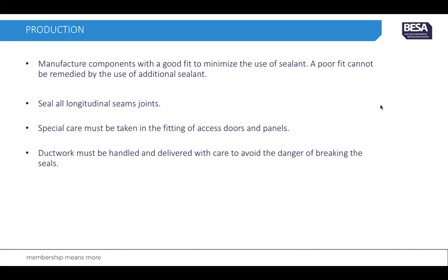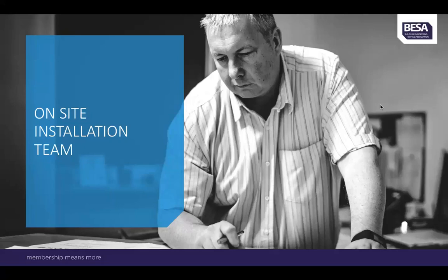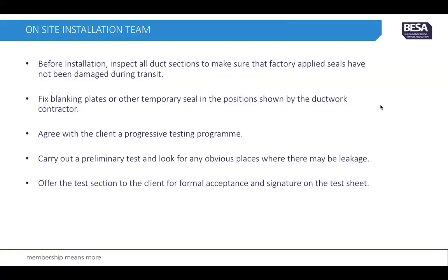The ductwork must be handled and delivered with care to avoid any danger of breaking the seals during transportation. The on-site installation team must, before installation, inspect all duct sections and make sure that factory-applied seals have not been damaged during transit or delivery. Blanking plates or other temporary seals in the positions shown on the ductwork by the ductwork contractor must be installed.